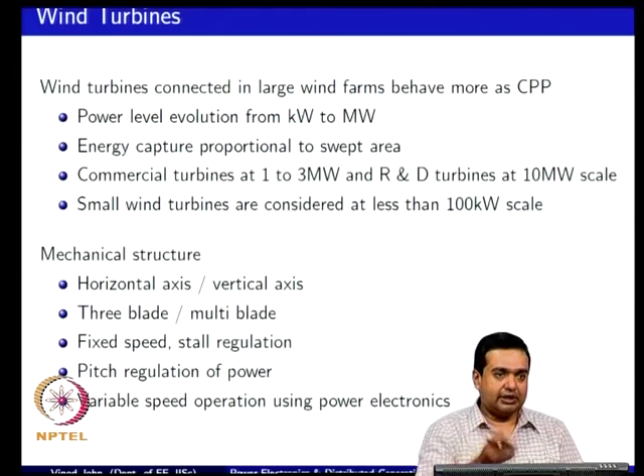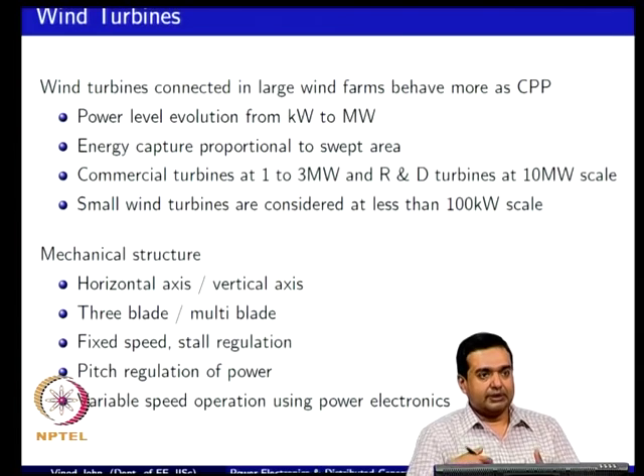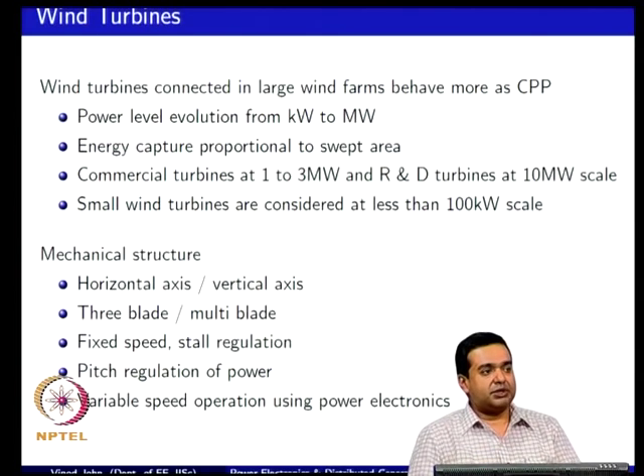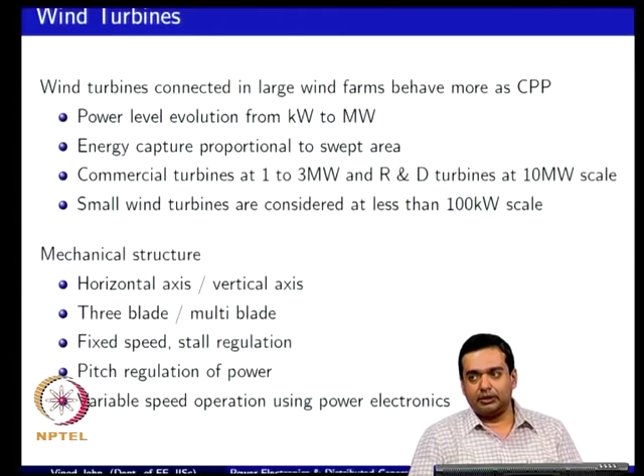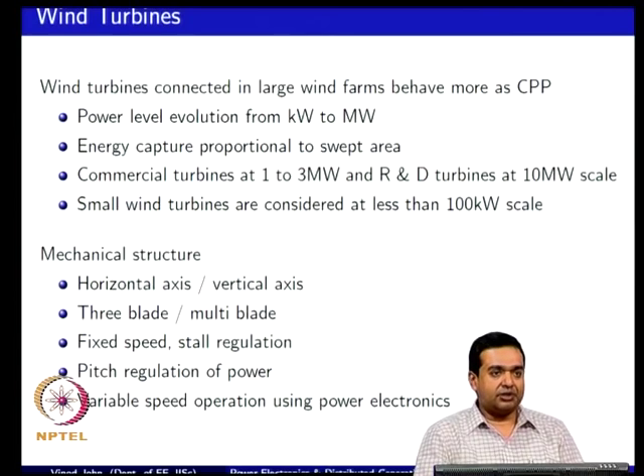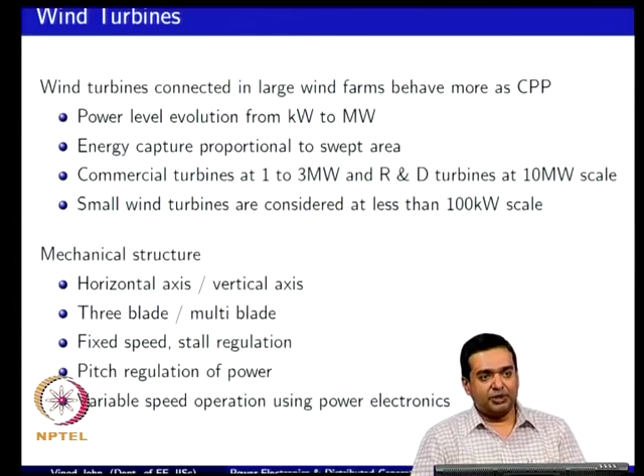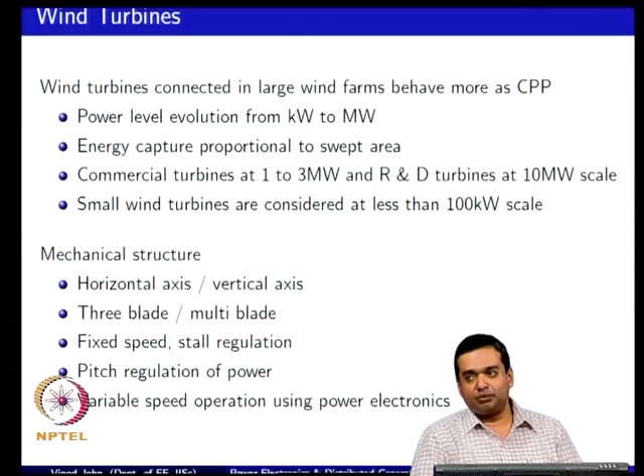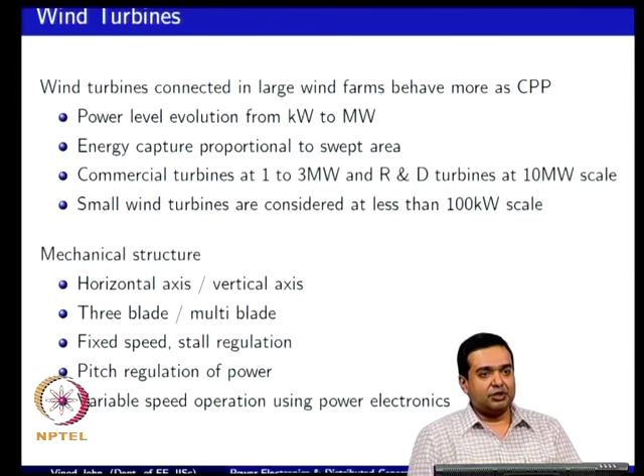Another blade option is pitch regulation, where instead of keeping the blade at a fixed position and designing it to stall, you physically change the pitch angle of the blade. If there is excessive power, you increase the pitch angle so the wind turbine does not capture it. More recently, people have looked at variable speed operation — the current state of the art — where you operate at a speed that gives the best energy capture. At low wind speeds you capture the best possible energy, and at high wind speeds you pitch out the blades to reduce the power captured.